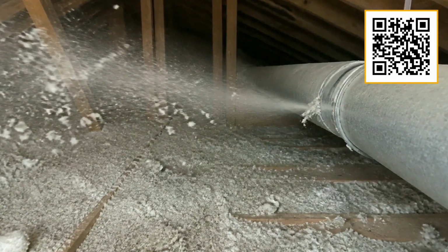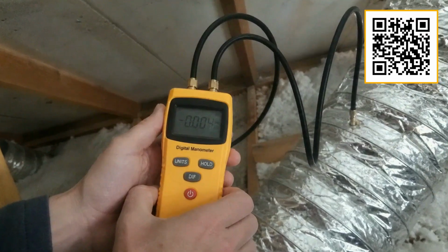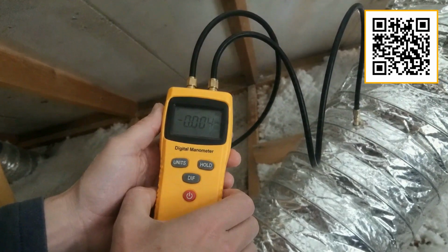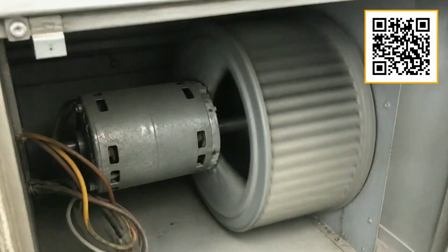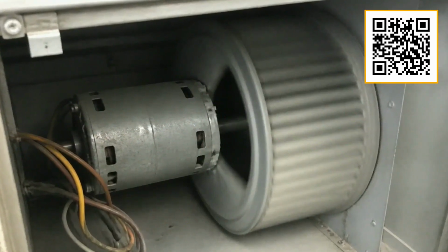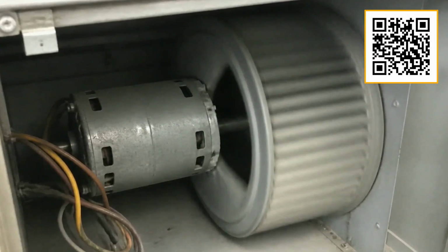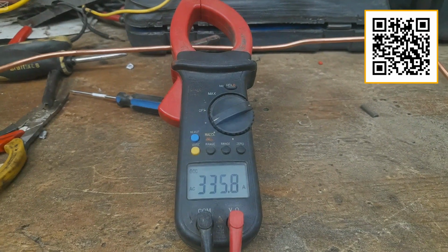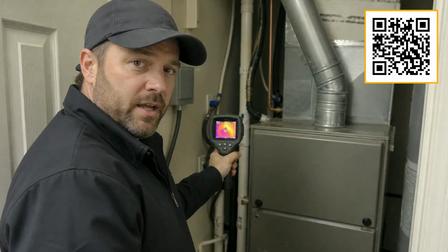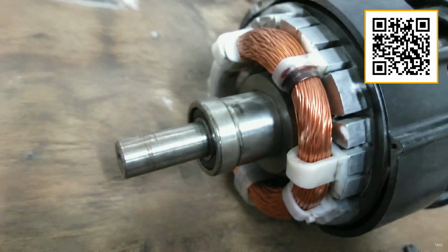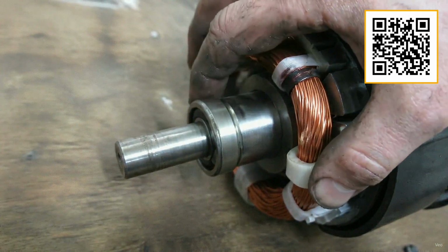There is a mechanical problem layered on top of that, and this is the one I think about the most. When internal duct pressure climbs too high, the blower motor has to work harder to push air through the system. It draws more electricity. It runs hotter. It cycles under more strain. Blower motors are durable pieces of equipment, but I have seen them wear out well ahead of schedule.